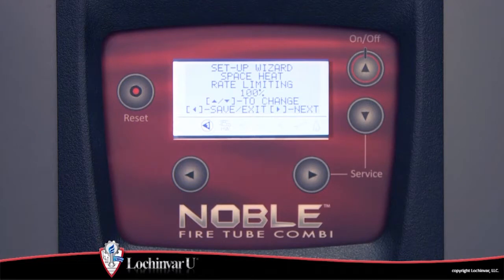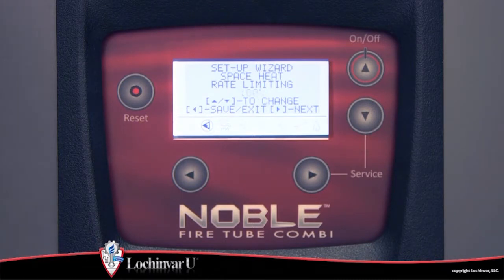This feature can minimize short cycling of the unit during a space heating demand, since it will most likely be smaller than that of the domestic hot water load. The adjustment range for this parameter is 10% to 100%.